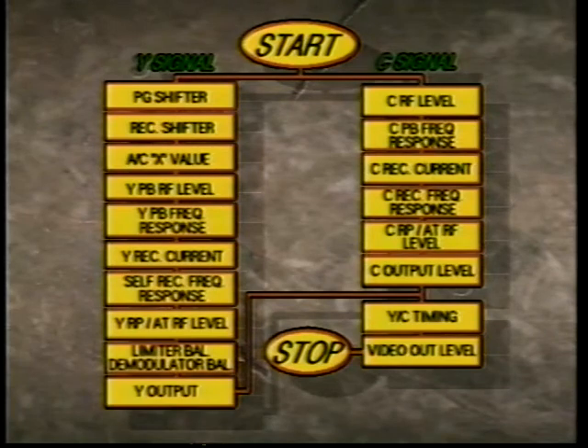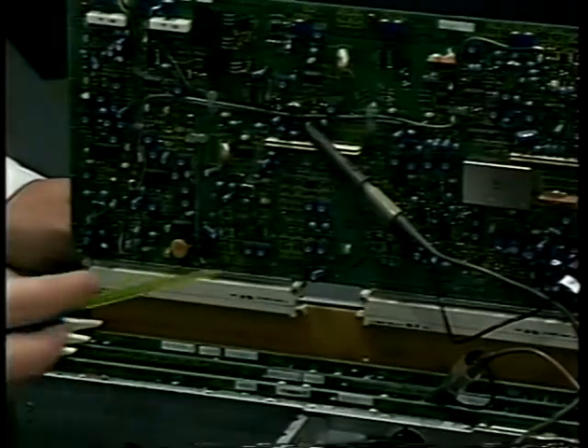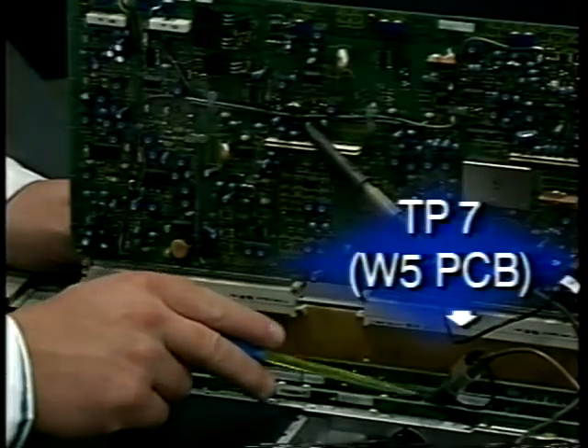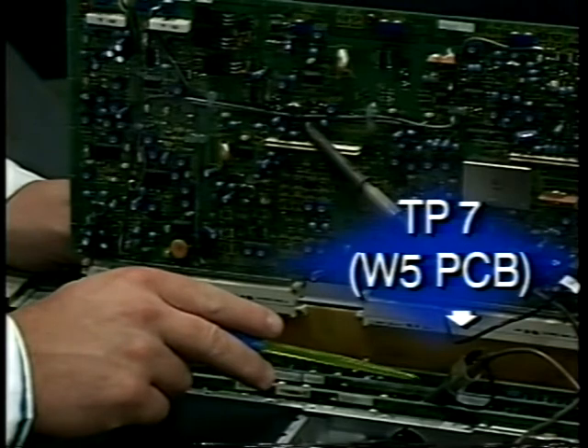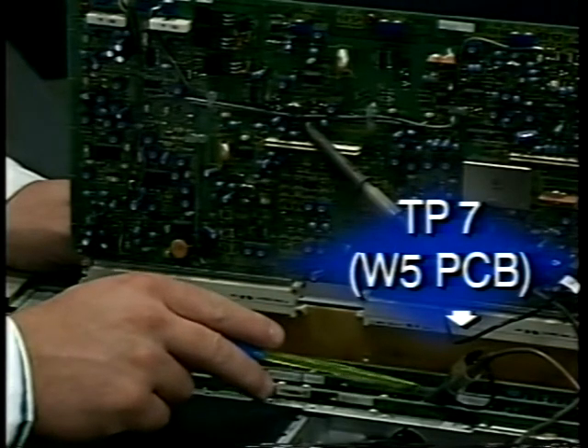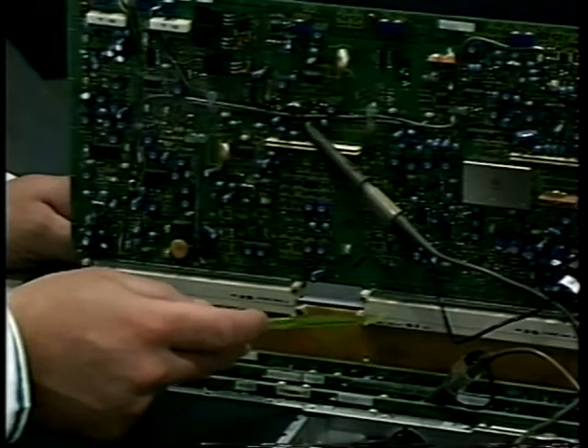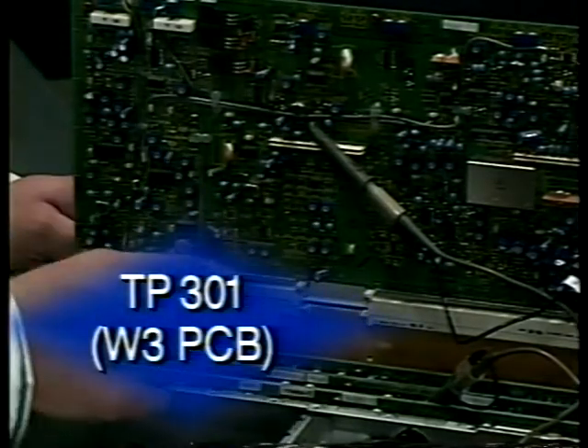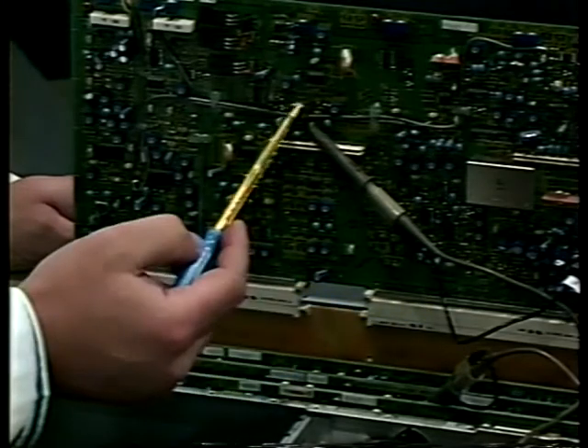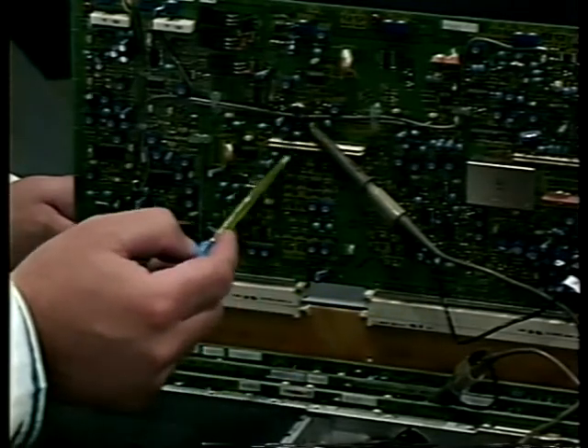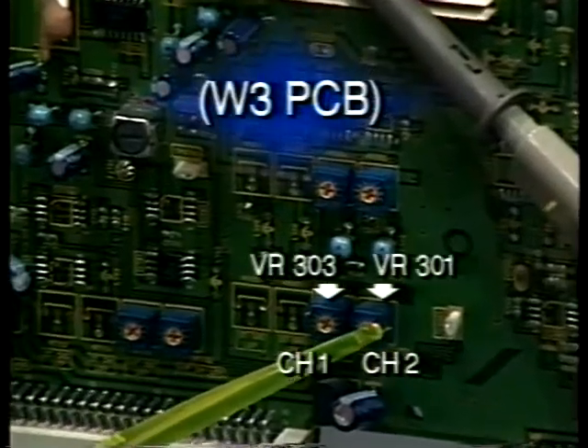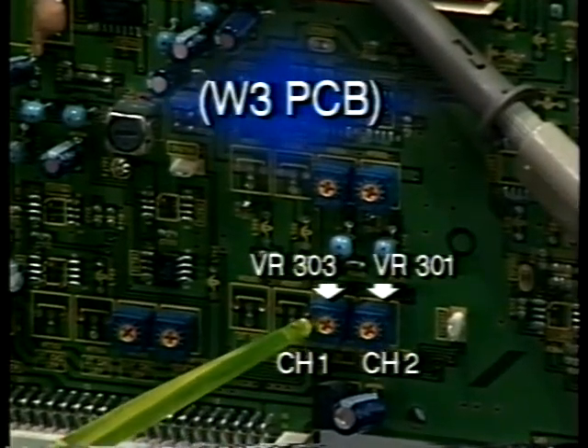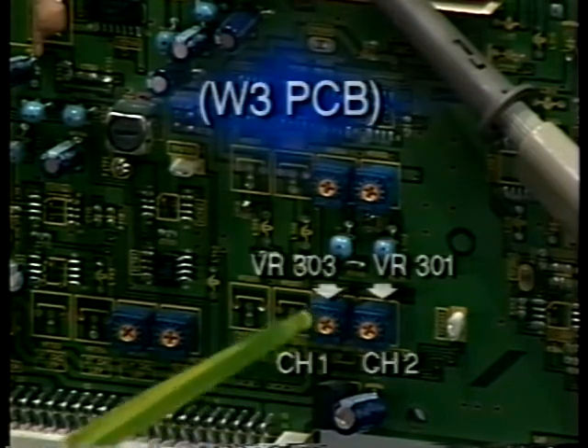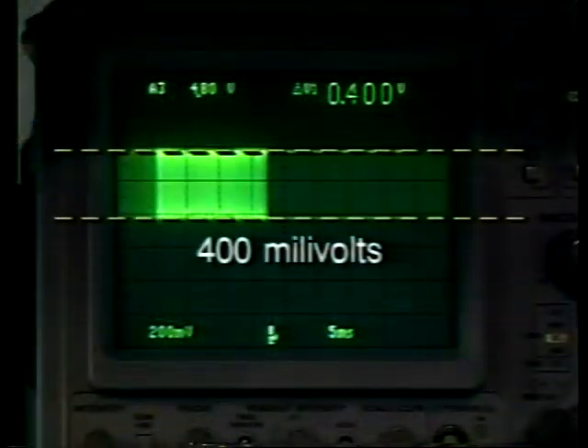The fourth step in the simplified head replacement flowchart is the Y playback RF level adjustment. For channel 2, you're going to be triggering off TP7 on the servo board. That's on the edge, so you can leave the board inside and use the extender board for the W3 board. Connect the channel 1 probe to TP301 on W3. The adjustment pots are 301, which is channel 2, and 303, which is channel 1. The adjustment is for 400 millivolts plus or minus 50 millivolts.